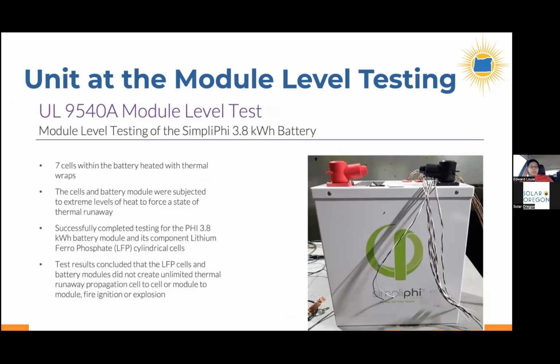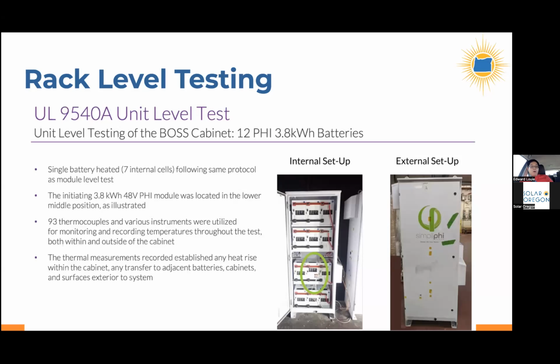And so here's an example. Okay, so like the company SimpliPhi, they did a test for the individual module, and then there's some tests concluding that this lithium iron phosphate cell did not create unlimited thermal runaway, so it's safe. And then they also did the same test at the rack level where they overheated the one battery in the rack. And then they also found some results that, the heat transfer to adjacent batteries, they recorded how that works. But wait, there's more.